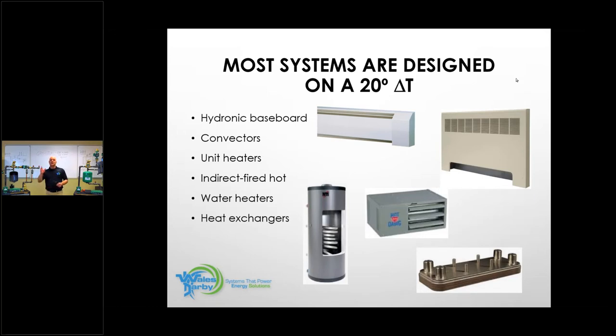So baseboard heat. If I have baseboard heat around this room that I'm standing in right now, I should enter that baseboard at one temperature, go through the baseboard and come back. The goal is on a design day, I will have a 20 degree delta T. Design day is going to be different. Wherever you are, there's a design temperature for your area. If I got up by my house, it's zero.